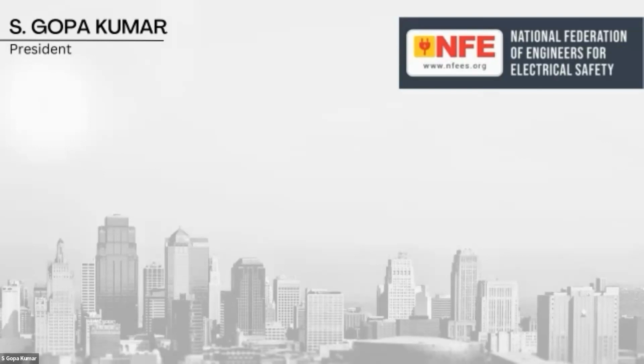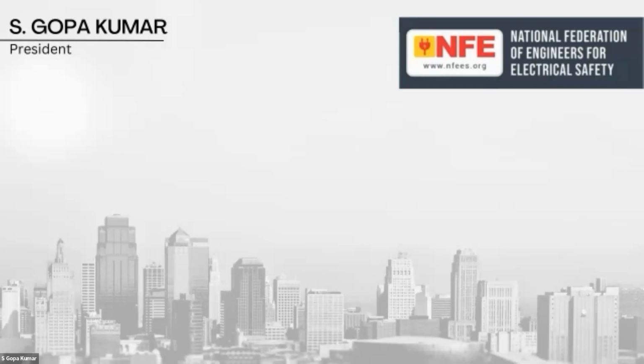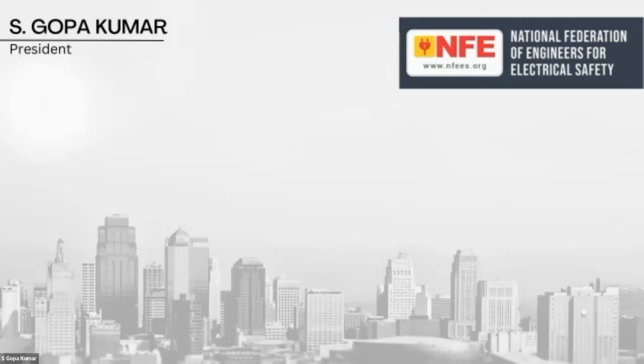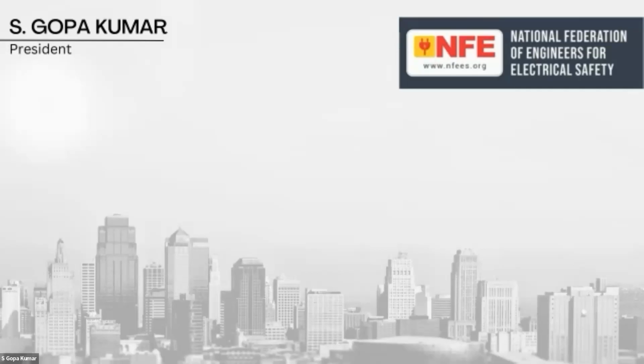My question is how the rockets launched from where we launch satellites are protected from lightning. You are talking about protecting the launch pad or the rocket? If it is the launch pad, the rocket is on the launch pad prior to launch. For example, an isolated catenary wire system is made. If you search on Google, there are some articles published about the catenary wire system installed in such installations. If your rocket launching station is, let's say, 50 meters, then there are 4 or 5 towers all around the area, much taller than 50 meters, and there are catenary wires.